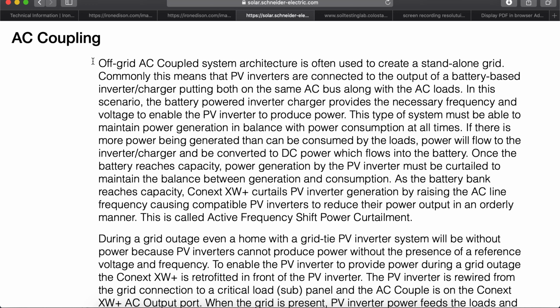If there is more power being generated than can be consumed by the loads, power will flow to the inverter charger and be converted to DC power, which flows into the battery. Once the battery reaches capacity, power generation by the solar PV inverter must be curtailed or slowed down to maintain the balance between solar generation and electrical consumption. As the battery bank reaches capacity, the Conext XW Plus battery inverter curtails or slows solar PV inverter generation by raising the AC line frequency, causing the solar PV inverters to reduce their power output in an orderly manner. This is called active frequency shift power curtailment.